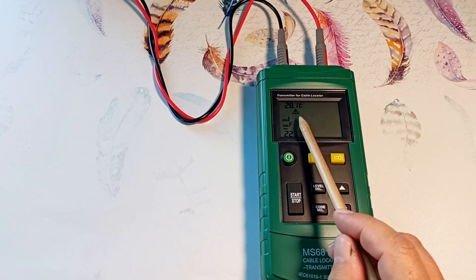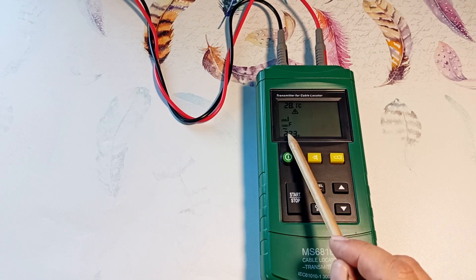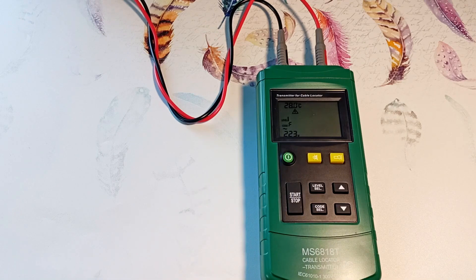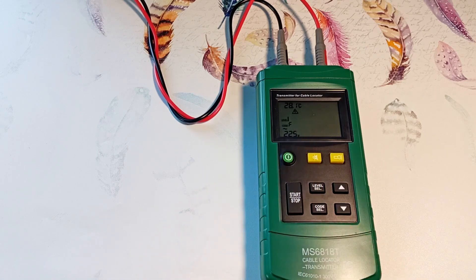We have a triangle displayed, indicating that the line is energized. The mains voltage is indicated here. And here the fact is that the current is alternating. If it is constant, then a minus sign will be displayed here. The mains voltage should not exceed 400 volts. The range of measured voltages is from 12 to 400 volts.